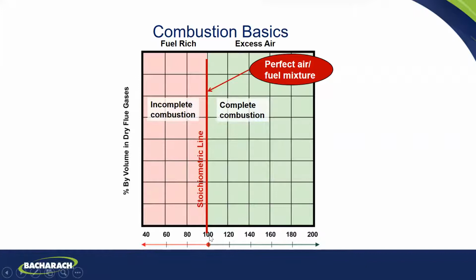And this green would be 100% of just the right amount of air. Here, 120 would be, I'm using 20% more air than the theoretical 100%. Sometimes you'll see things written or an analyzer will just say 20%. Sometimes in this chart I have 120. It's saying the same thing, 20% more than the 100% of the theoretical air you need. 40% more would be the 140, 60, and so forth. So we want to be on this green side when we do our equations. Over here we have more air than we theoretically need for combustion, but we need it for complete combustion.